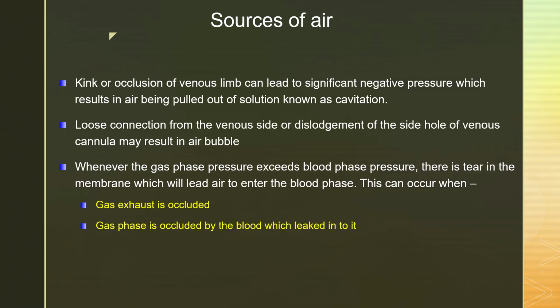Third is too much positive pressure in the gas phase line. In the gas phase line, the oxygen or the air is moving. If that gas phase line exhaust is blocked, what will happen? The pressure will build up and the membrane will rupture, and that will lead to air in the circuit. Then what are other sources from where the air can enter?